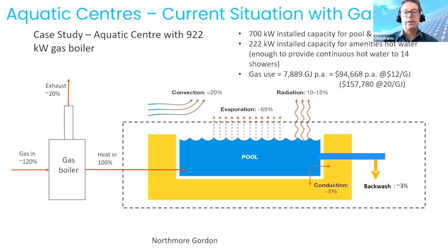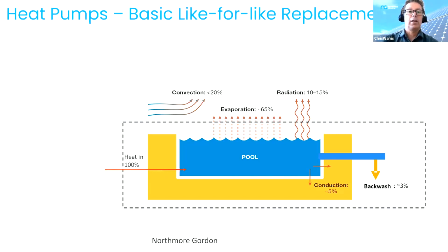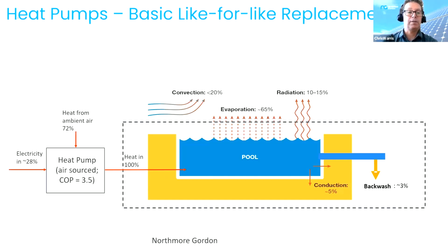The gas use in this facility is 7,889 gigajoules per annum, and it costs them nearly $100,000 a year at $12 a gigajoule. The gas price is about to rise, so obviously with a high gas price, those costs are higher. With a heat pump, you do a like-for-like replacement of the same size, and for 922 kilowatts of heat pumps, it would cost somewhere in the order of $900,000.